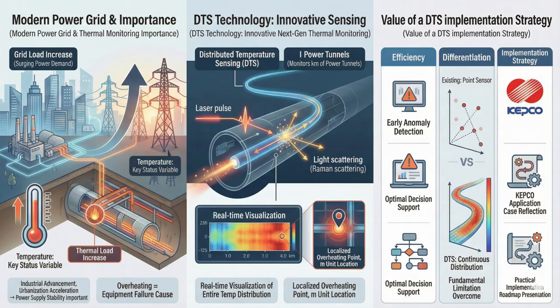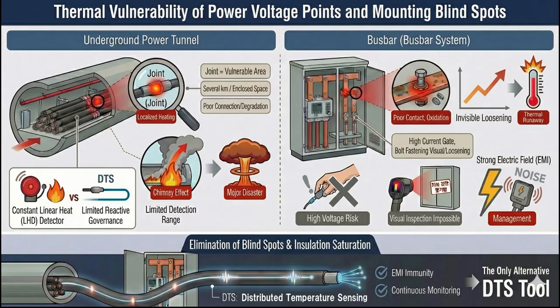Beyond simple detection, DTS also delivers value that connects to operational efficiency and asset management, along with a practical strategy for adoption. There are two major thermal weak points in power facilities. The first is underground utility tunnels and cable ducts, where local hotspots can occur at joints or damaged sections. Yet conventional detection methods often leave blind spots. The second is busbar systems, where overheating due to poor contact is a serious risk. But sensor installation and stable measurement are difficult. Because of high voltage and strong electromagnetic environments, DTS-based continuous monitoring is a leading solution that eliminates these blind spots.